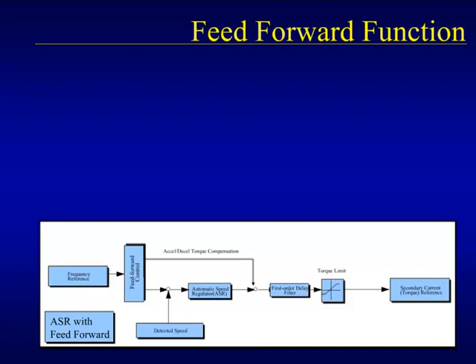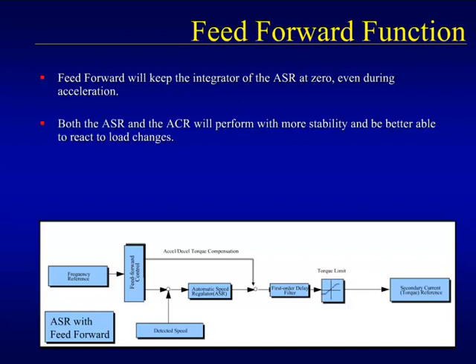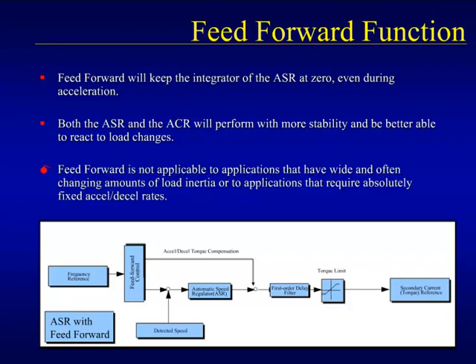One of the ways that the feed forward function achieves a stable frequency profile with little overshoot is that it will keep the integrator of the ASR clamped at zero even while the motor is accelerated. A benefit of the feed forward function is that it will stabilize the automatic speed regulator and the drive's automatic current regulator, allowing them both to respond quicker to load changes. Applications where the load inertia varies greatly may not benefit from the feed forward function due to the inability to specify an accurate system inertia. Also, applications that require extremely tight acceleration and deceleration ramps will not benefit from the feed forward function.